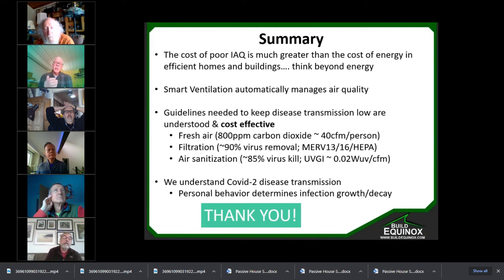We haven't done our own microbial studies. These studies with viruses take very specialized facility, even with a safe virus, in order to run a virus through something to then culture it. It's different than culturing a bacteria. You've got to culture it in cells, and the handling is very difficult. So we're going on other people's data, like EPA, who did some of the original work, and then some ASHRAE test work. We're basing it on those levels. But a fraction of a second is more than enough to substantially kill a virus.